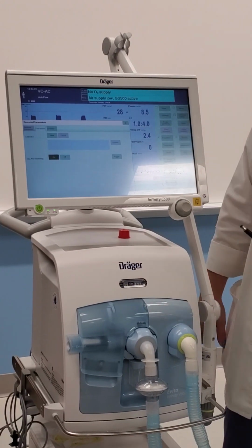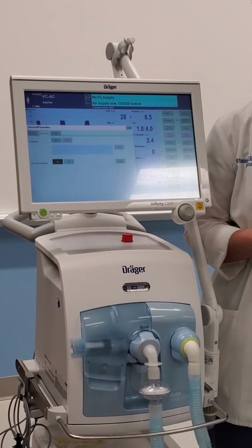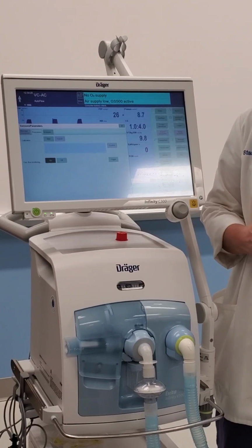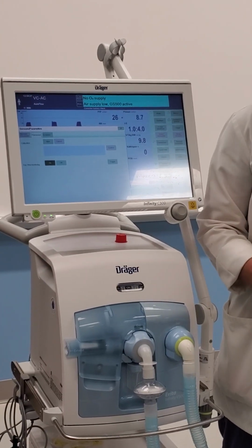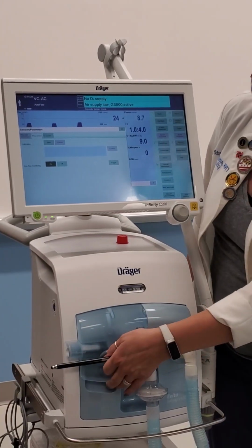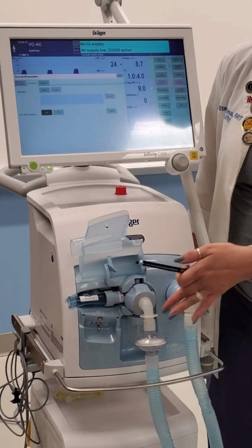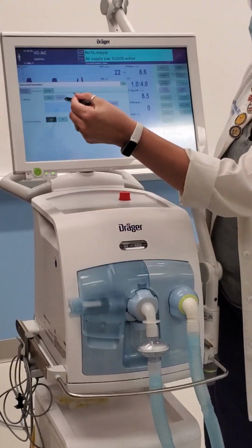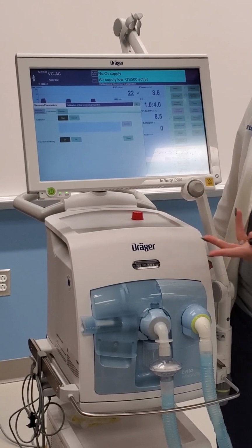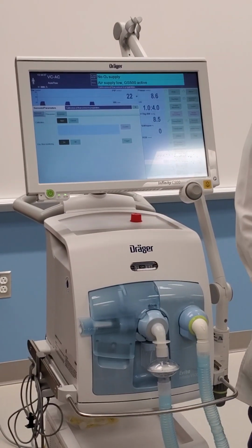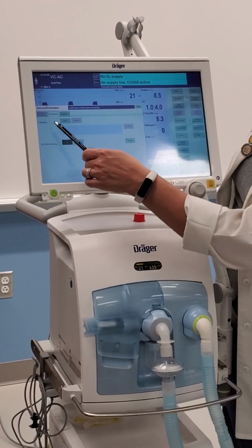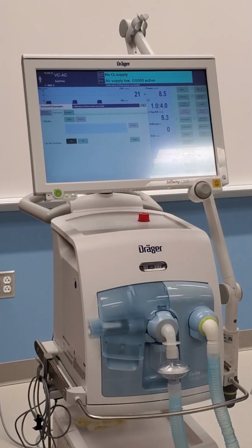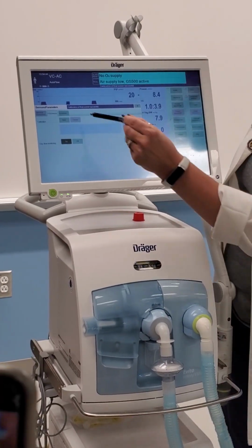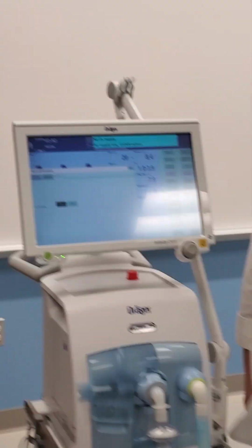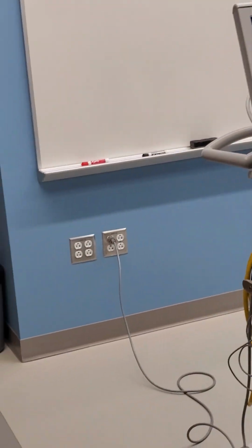Sensors and parameters. Remember how I said the flow sensor will probably inevitably give you issues? Don't panic, okay? Just lift it up, take it out, put it back in, and then you hit start calibration, confirm. It takes literally like 5 seconds. And it'll say calibration of flow sensor successful. You can also adjust your O2 sensor to be on or off for monitoring. We're always going to keep it on, right?